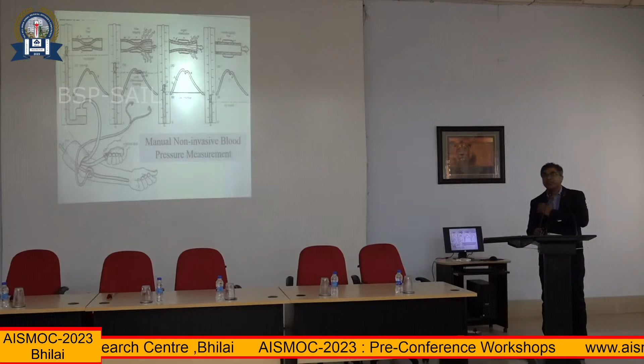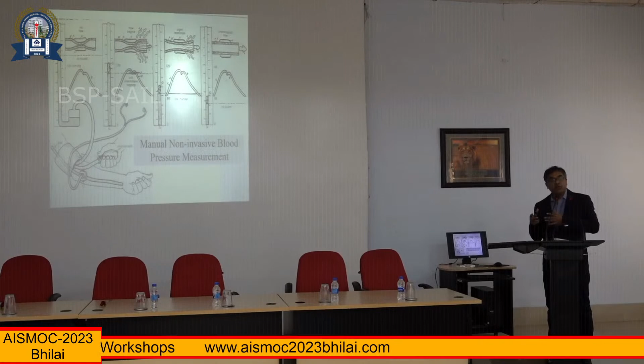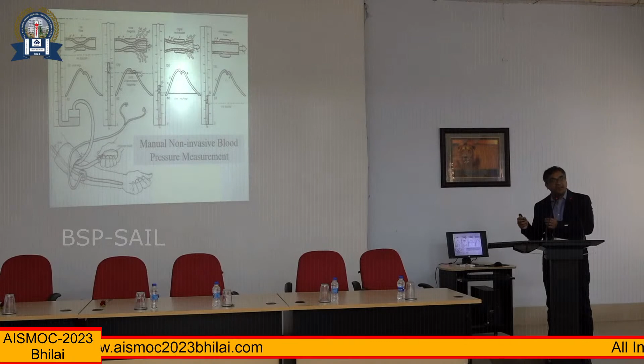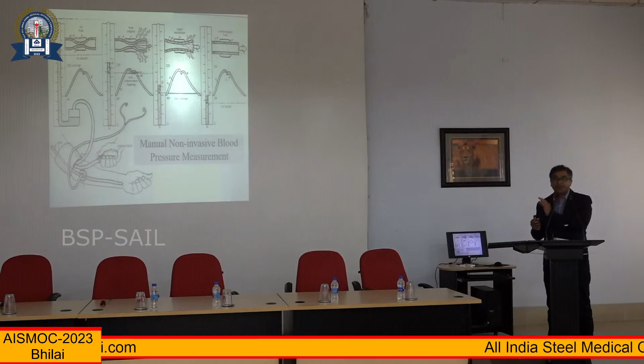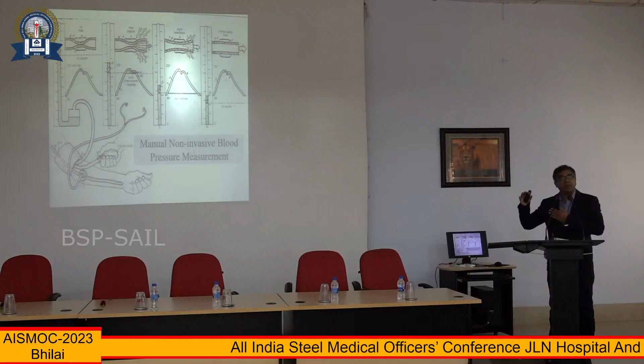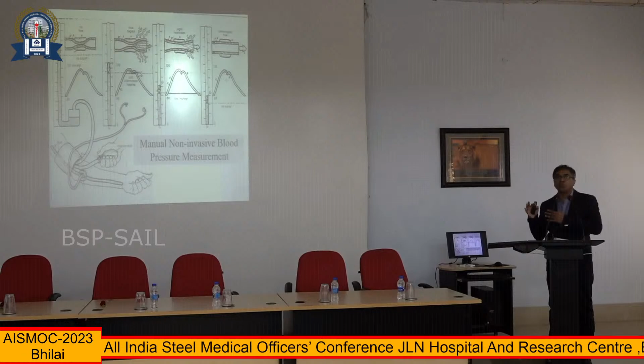So when we look at non-invasive, we've always been taught the way it is. So it actually looks at flow. When you put a cuff around the arm, you inflate the bladder to obliterate the flow in the artery, and then you release the pressure in the cuff slowly till the flow starts. And once the flow starts, the sounds that you hear are described as the Korotkoff sounds. But essentially, when you start hearing the sound, you reasonably assess that as systolic pressure, and when the sounds get muffled, you take it as diastolic.